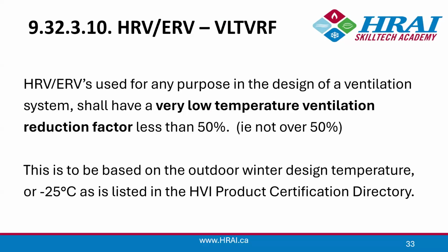One other little new provision is that HRVs and ERVs that are used for any purpose in the design of a ventilation system shall have a very low temperature ventilation reduction factor that's less than 50%. This is to be based on the outdoor winter design temperature, or if it's not listed at that temperature, minus 25 Celsius in the HVI product certification directory. So what does that mean? Essentially, when it's very, very cold, the HRV has to stop running to defrost.